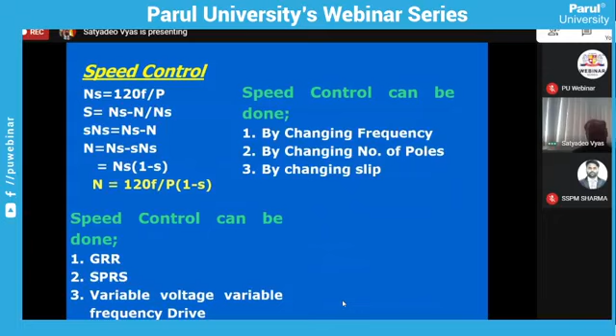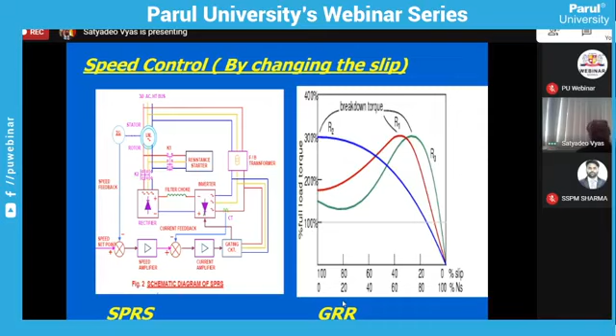This is an example of the slip control method which industry uses in the slip power recovery system. This system is used where a speed range between 60 to 100% is required. Below this, the drive is run on the LRS, and after achieving 60% speed, the LRS is changed over to the SPRS system. After that, 60 to 100% speed can be varied, but it is applicable only when you use a slip ring induction motor.